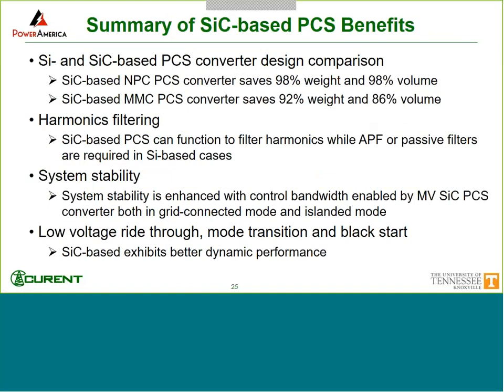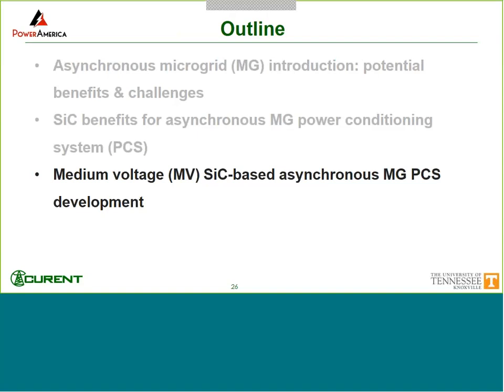So if I summarize the potential benefits of using a silicon carbide-based PCS in an asynchronous microgrid: for the converter, huge savings in terms of weight and volume. For the system level, it can provide harmonic filtering without adding much capacity. It can also help with system stability and will have better low voltage ride-through and mode transition capability. With that, let me move to the PCS converter design development itself.